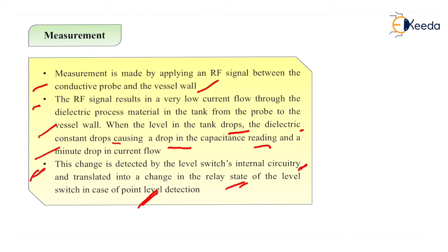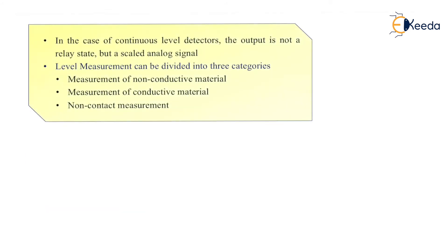To summarize: the RF signal causes a low current flow through the dielectric process material from probe to vessel wall. When the liquid level drops, the dielectric constant drops, causing a drop in capacitance reading, which is detected by the level switch internal circuitry and translated into a change in relay state for point level detection. For continuous level detectors, the output is not a relay state but a scaled analog signal. This level measurement is divided into three categories: measurement of conductive material, measurement of non-conductive material, and non-contact measurement.